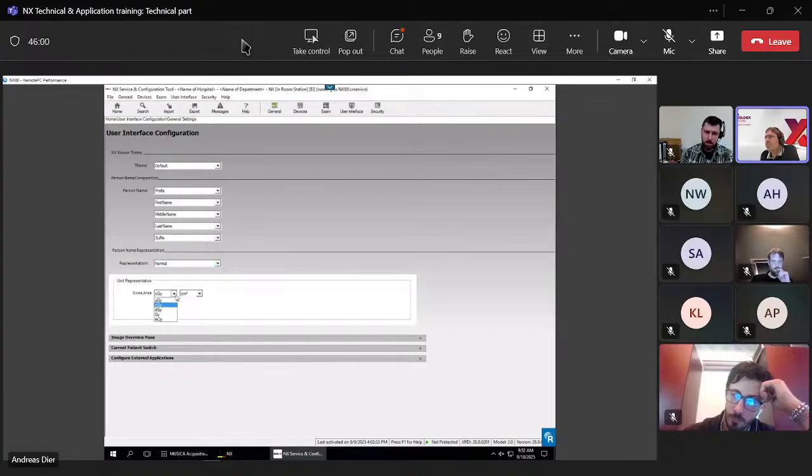So we have here the choice between microgray, centigray, decigray, gray, and milligray. And for the area, square centimeters, square decimeters, square meters, and square millimeters. This means you just look into the details and information of the DAP meter that you want to install.